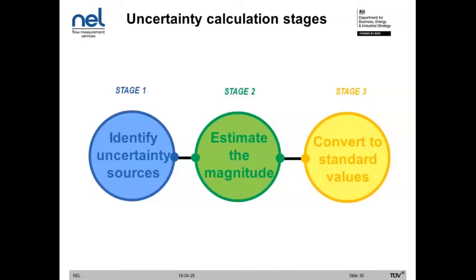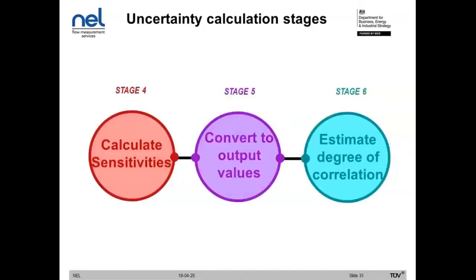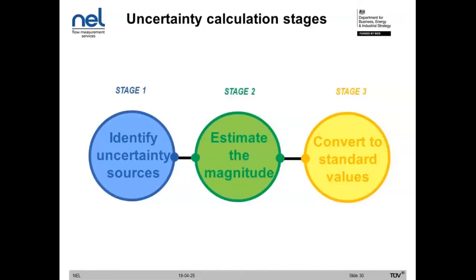So once you have your uncertainty sources and reasonable estimates for their magnitude, the next step is to convert to standard values. So this would be converting to standard uncertainties. You'd be converting from expanded uncertainties using your coverage factor to the standard uncertainties at 68% confidence level. The reason you do this is that if you want to combine the uncertainty sources, they all have to have the same coverage factor. You can't combine uncertainties that have 95% confidence with uncertainties that have 68% confidence. So the most standard way of doing things is to reduce them all to standard uncertainties.